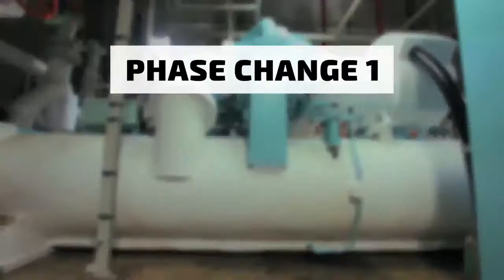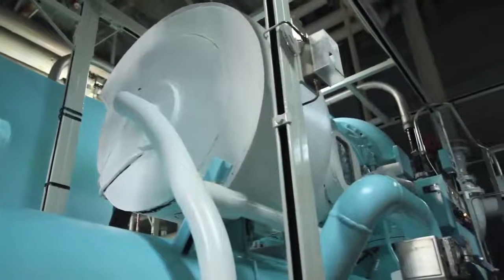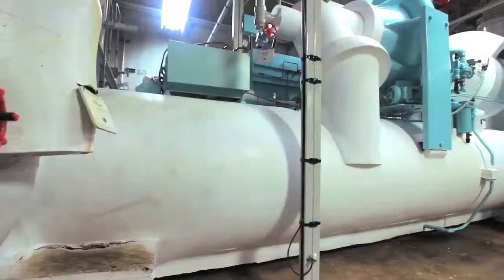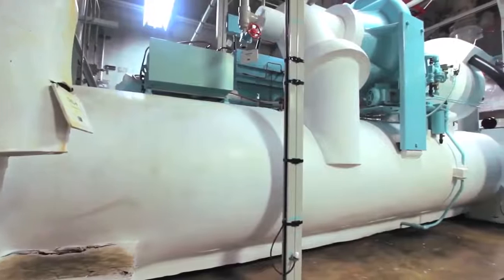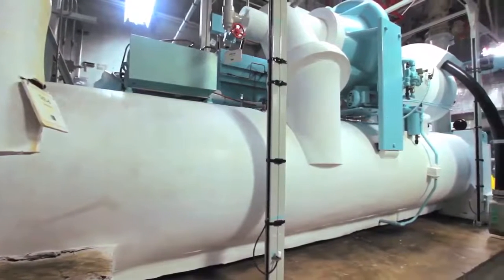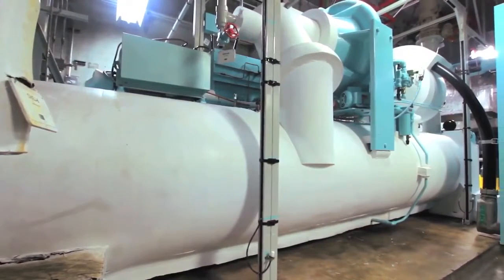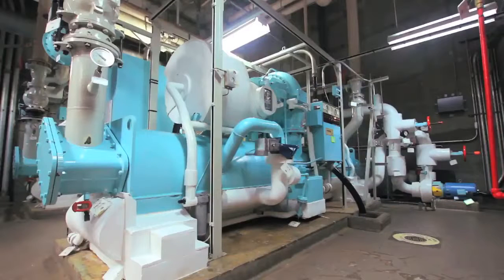This is one of the phase changes that occurs in the machine. That gas exits into the condenser. The condenser contains a tube bundle that runs the length of the machine. Different machines have different design tubes. Some have fins on the inside, some have fins on the outside. Usually they're externally finned. The tubes are periodically cleaned to remove deposits on the interior tube surface.